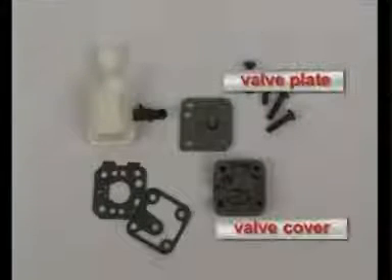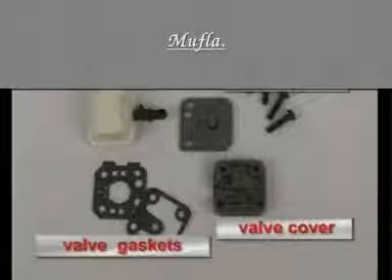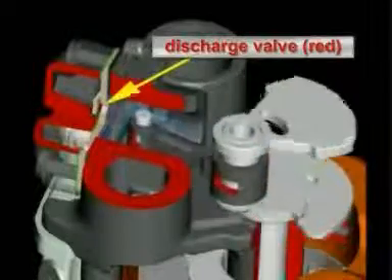The valve unit essentially consists of a valve plate, a valve cover, a muffler, as well as two valve gaskets. The suction and the discharge valve are installed on the valve plate. Both valves are reed valves made out of spring steel and they open and close the openings of the valve plate during the suction and discharge process respectively, so that the compressed refrigerant moves into the discharge chambers of the block. The muffler forms a connection between the suction connector of the shell and the suction side of the pump unit, and its task is to minimize the suction noise.